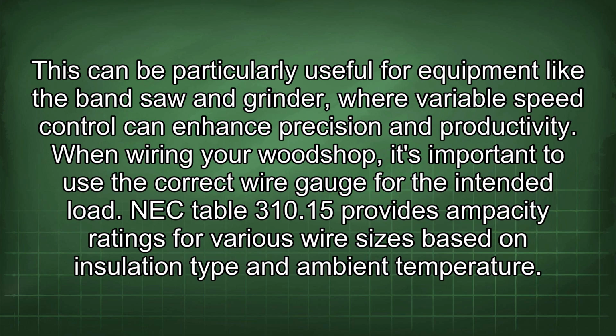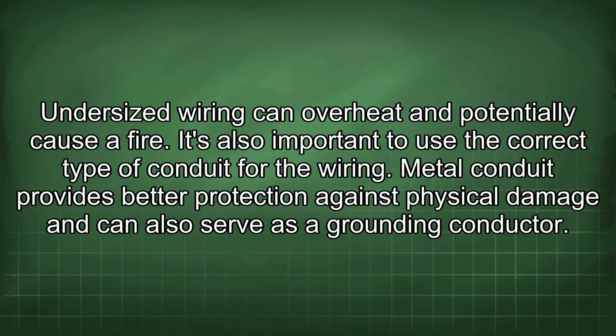When wiring your woodshop, it's important to use the correct wire gauge for the intended load. NEC Table 310.15 provides ampacity ratings for various wire sizes based on insulation type and ambient temperature. Undersized wiring can overheat and potentially cause a fire. It's also important to use the correct type of conduit for the wiring. Metal conduit provides better protection against physical damage and can also serve as a grounding conductor.